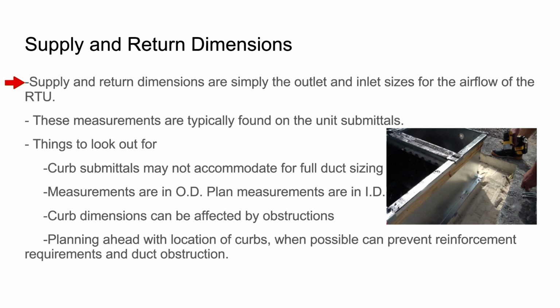Supply and return dimensions are simply the outlet and inlet sizes for airflow of the RTU. They're found on unit submittals or footprint, but you have things to look out for. Curb submittals may not accommodate for full duct sizing, meaning your submittal for your actual flat curb or curb adapter may not be the same size as what you're looking at on the bottom of the footprint. So you need your submittal for the equipment and your submittal for its curb. Usually there's a slight difference, probably just because the physical exit of the unit is usually smaller. I don't know why, but it is.